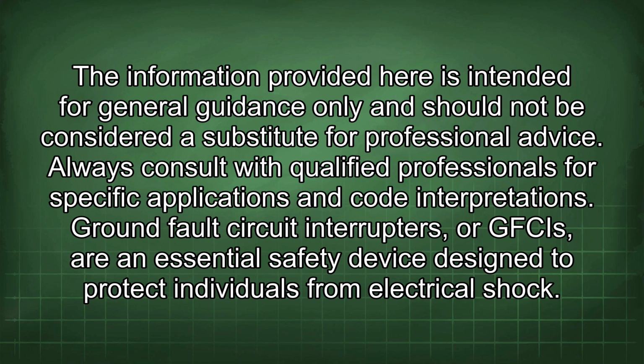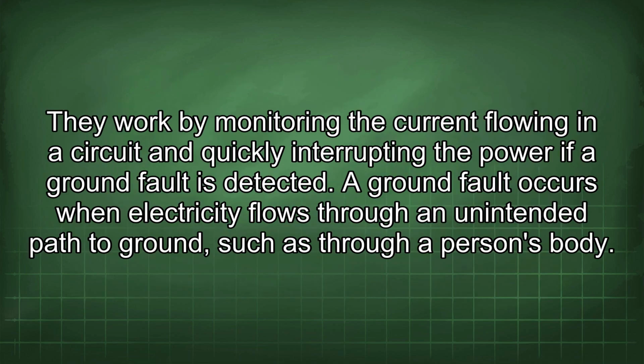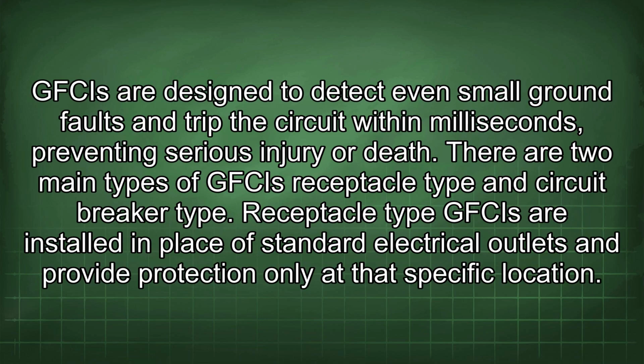Ground fault circuit interrupters, or GFCIs, are an essential safety device designed to protect individuals from electrical shock. They work by monitoring the current flowing in a circuit and quickly interrupting the power if a ground fault is detected. A ground fault occurs when electricity flows through an unintended path to ground, such as through a person's body. GFCIs are designed to detect even small ground faults and trip the circuit within milliseconds, preventing serious injury or death.